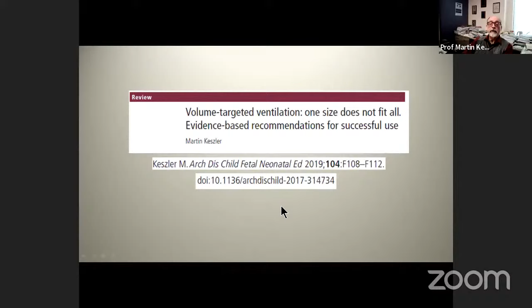For those of you who use the Drager ventilator, this is an important advance. Not all, some of the other machines that use volume targeted ventilation don't have this, and they have to be more careful. But we all struggle with the leak around the endotracheal tube in our patients. Volume guarantee and other volume targeted modalities typically use exhaled tidal volume, which is less affected by leak, but there still is leak even during the expiratory phase because it's driven by the end expiratory pressure, PEEP. So if you're using higher PEEP, you will have more leak even during exhalation.